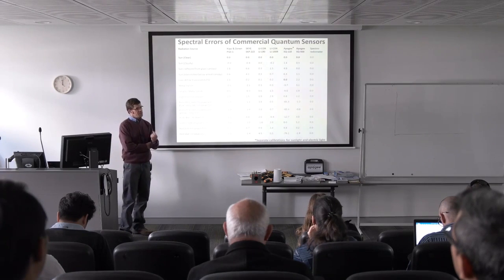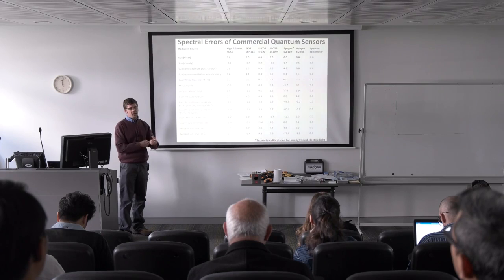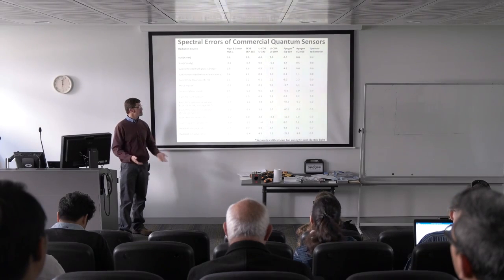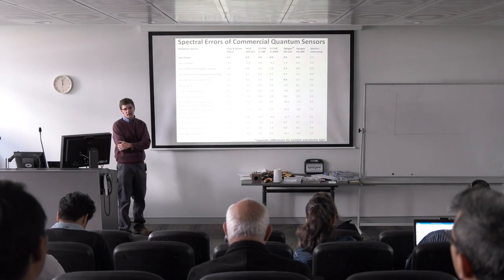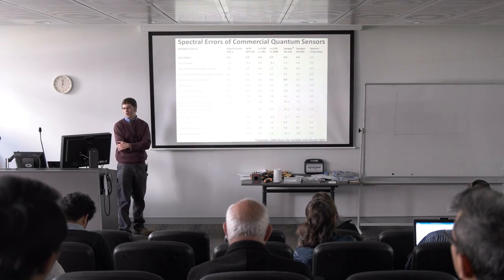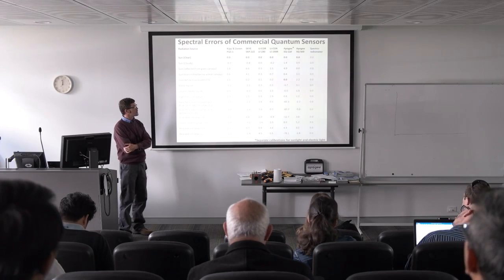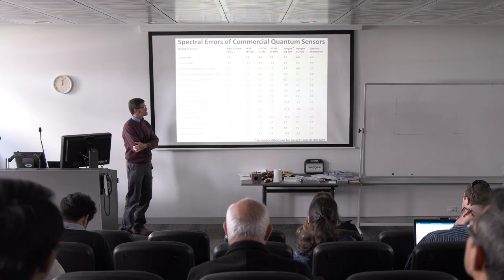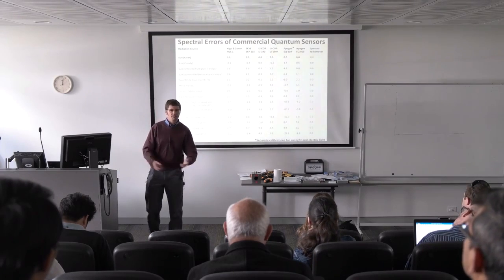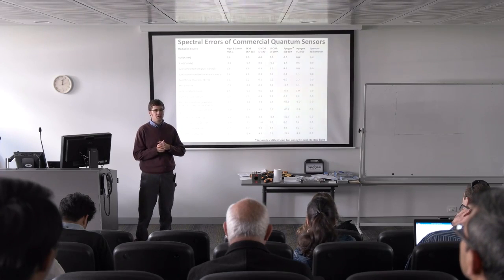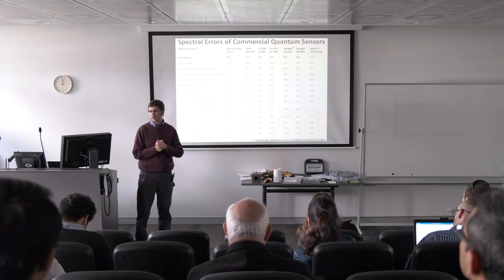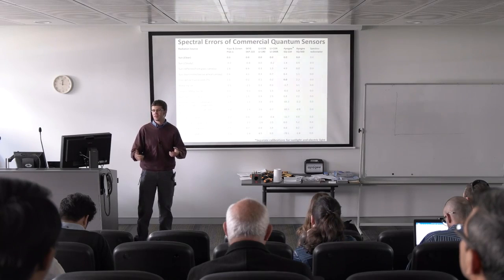As I mentioned when I was talking about the differences between quantum sensors and spectroradiometers, if your spectroradiometer is calibrated accurately, because it's measuring all of the wavelengths individually, then spectral error doesn't exist. We don't have to worry about spectral error with a spectroradiometer. So you might be asking, well, if this is the case, why would I ever use a quantum sensor to measure PAR? Wouldn't I just use a spectroradiometer every time?